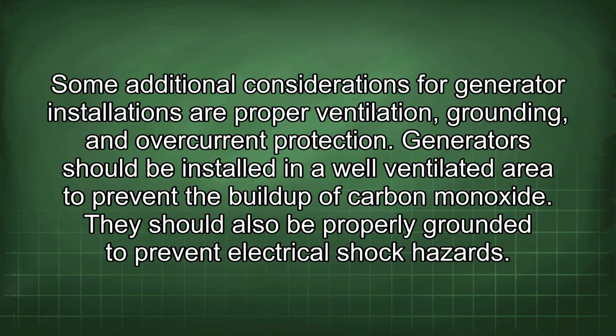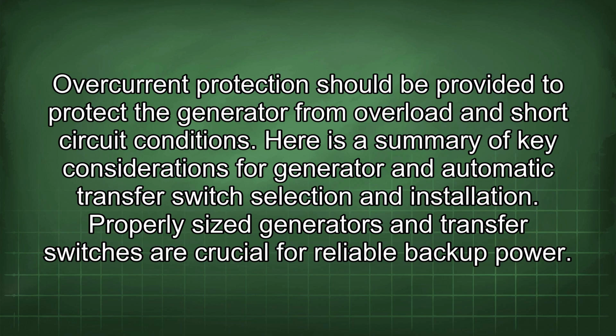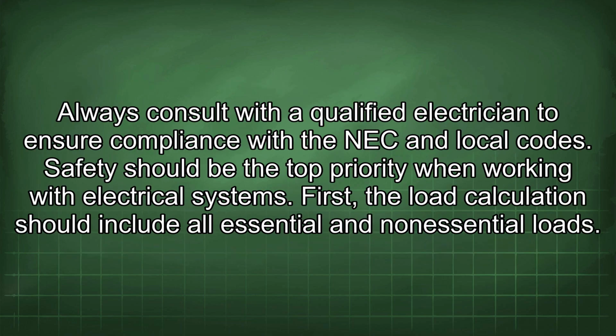Some additional considerations for generator installations are proper ventilation, grounding, and overcurrent protection. Generators should be installed in a well-ventilated area to prevent the buildup of carbon monoxide. They should also be properly grounded to prevent electrical shock hazards. Overcurrent protection should be provided to protect the generator from overload and short-circuit conditions. Here is a summary of key considerations for generator and automatic transfer switch selection and installation. Properly sized generators and transfer switches are crucial for reliable backup power. Always consult with a qualified electrician to ensure compliance with the NEC and local codes. Safety should be the top priority when working with electrical systems.